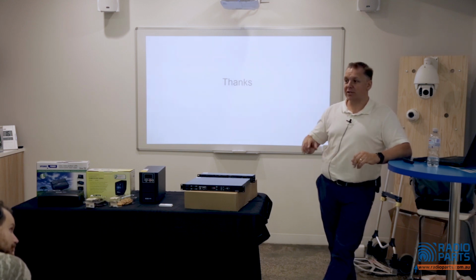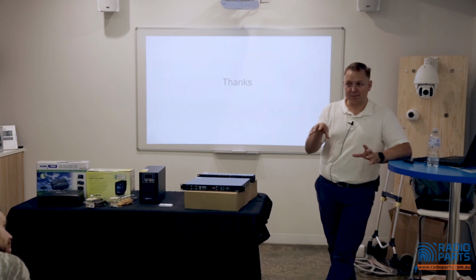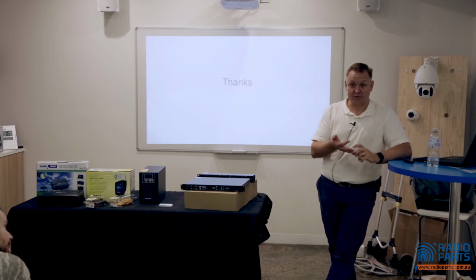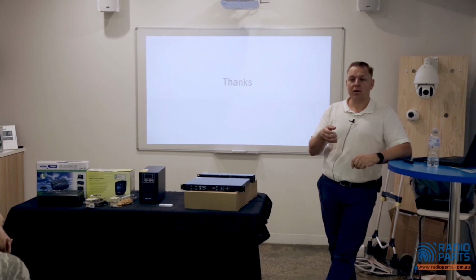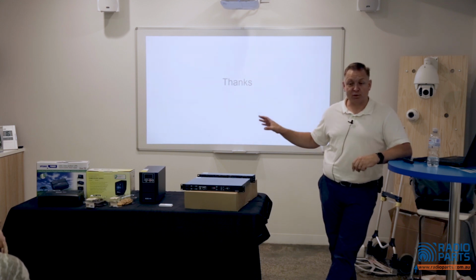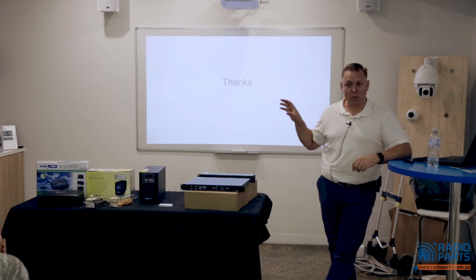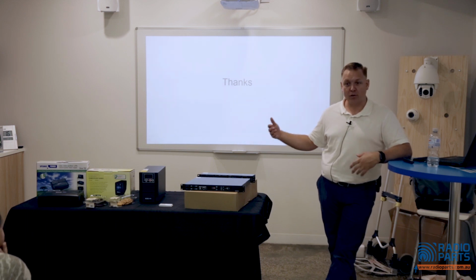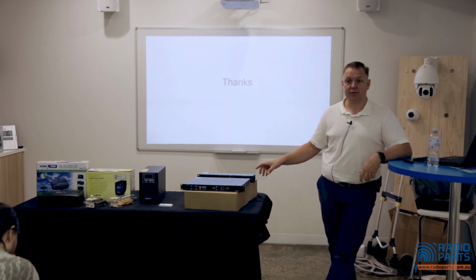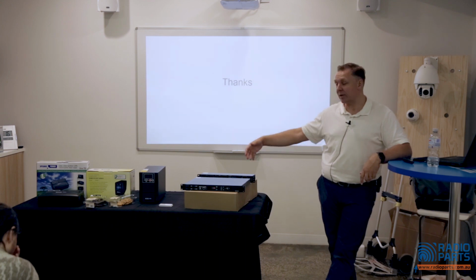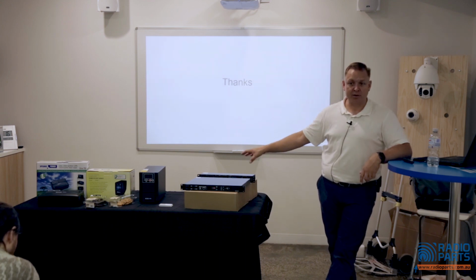So if there's a problem, then you can have other issues. But if things are working properly, there should be no effect at all. In fact, when we start talking about getting really deep dive science stuff, we start talking about harmonic distortion and things like that. Early UPSs were terrible, and they would actually be one of the worst things in an installation for harmonics. It's now one of the best things. So harmonic distortion, once we get all the dual conversion units, less than 3%.